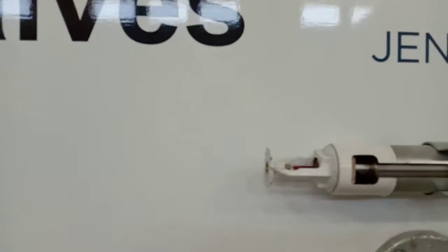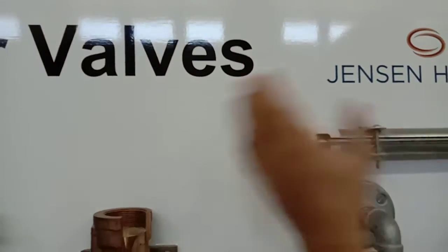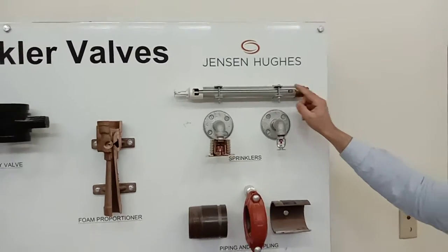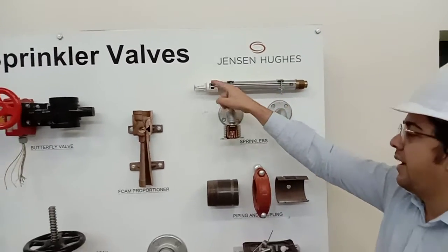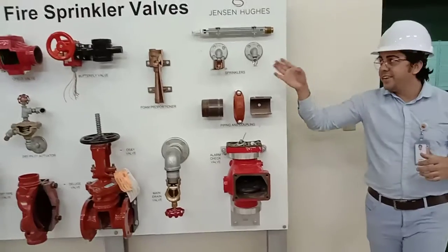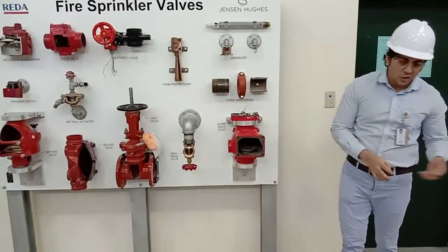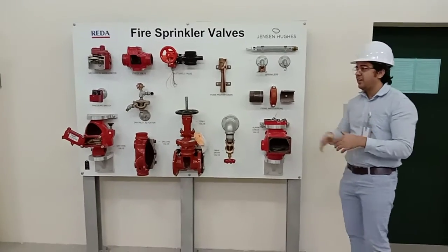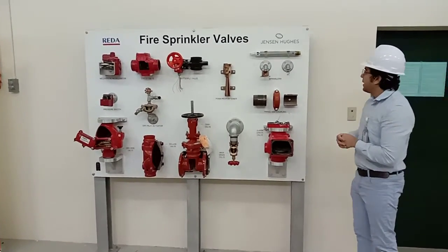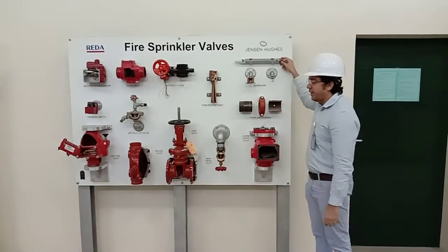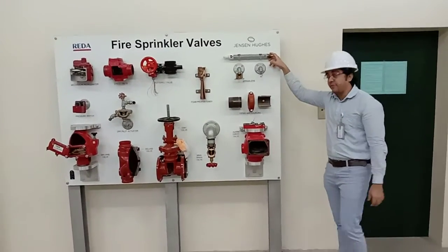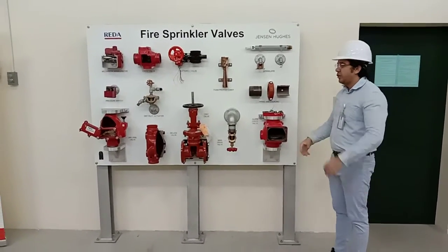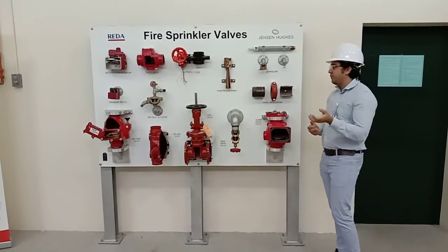In case of fire, the bulb will fuse and the plug will go out. As a result, the cap will open, allowing water to discharge into the barrel and then fight the fire. The idea is that we cannot install a dry pipe valve in all applications. For small areas with freezing temperatures, we can use this type of dry sprinkler to avoid installing a dry pipe valve, which is costly and requires more maintenance.